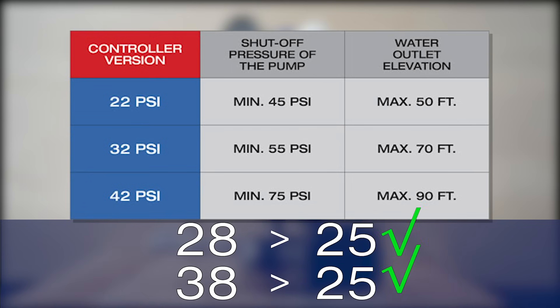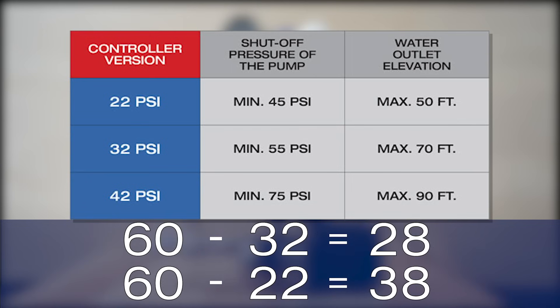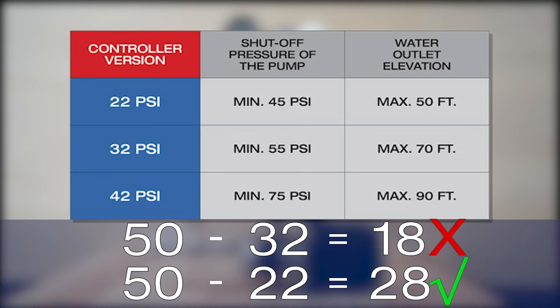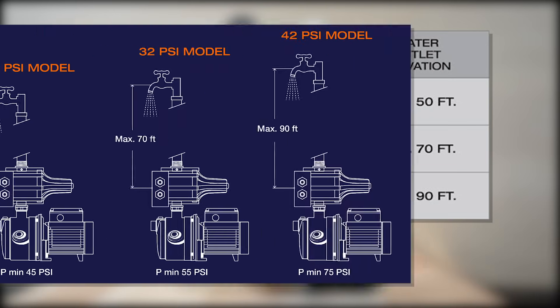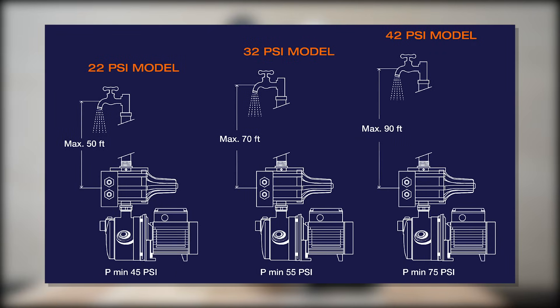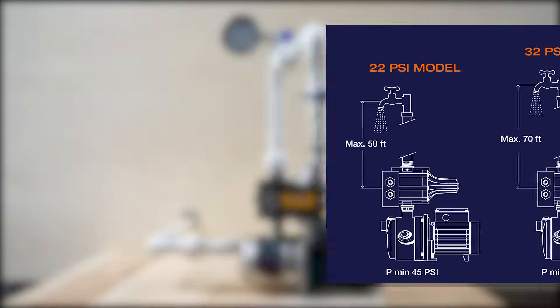However, if the shut-off pressure of your pump is 50 psi, you will have to select the 22 psi version. Also keep in mind that the elevation between the controller and the highest faucet cannot be more than 50 feet, 70 feet, or 90 feet depending on the controller model selected. Otherwise, the controller will never operate properly.